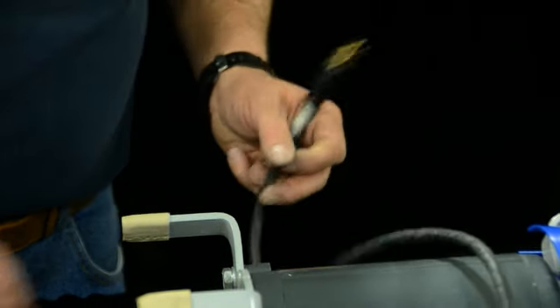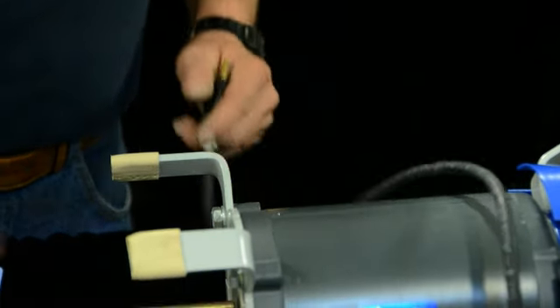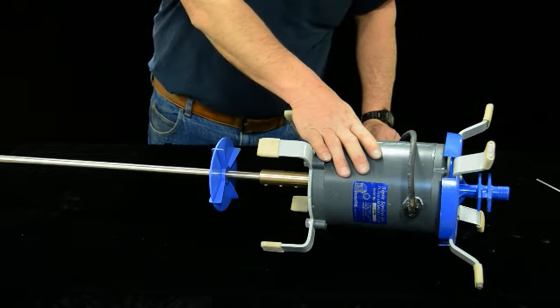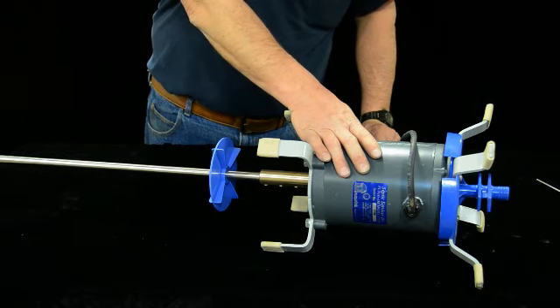So then you got it all done, you put it back together. You want to plug it in, you want to check your amp draw, make sure it's within nameplate amperage. Then you can go put it back in the tank.